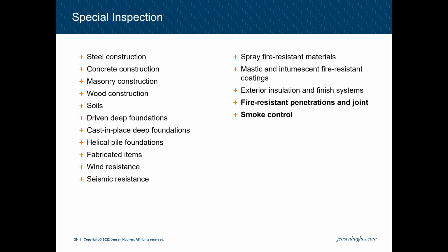These are the special inspections that are required by the building code. And you can see there's steel, construction, concrete, masonry, soils, a lot of foundation and primarily structural items. Because of that, and a lot of times not a super detailed review for a statement of special inspections, stuff like fire resistance penetrations and joints and smoke control does get missed from the statement. Unfortunately, because of that, sometimes that gets missed during construction. And special inspection for fire resistance penetrations and joints or smoke control sometimes does not even get identified till later on in the project.